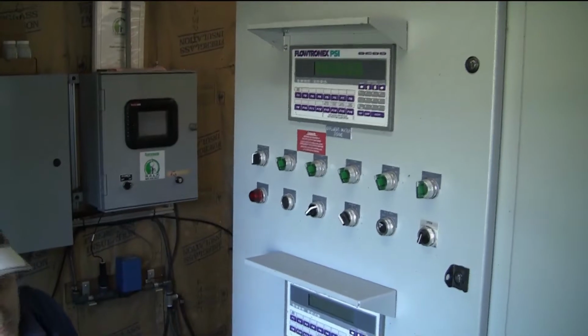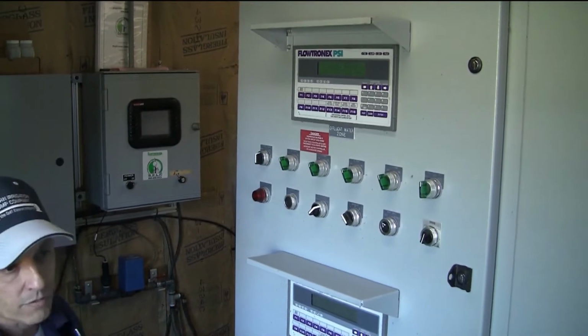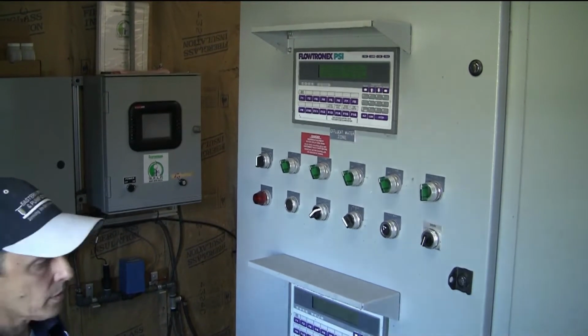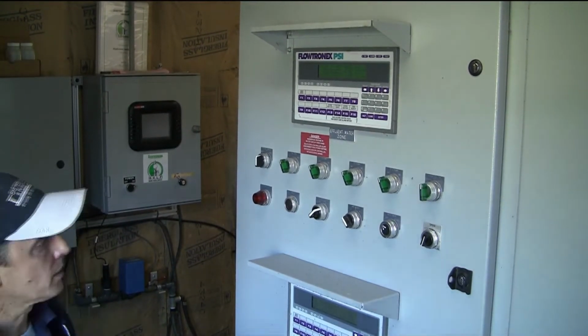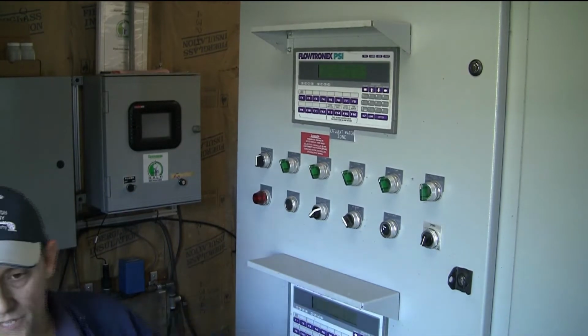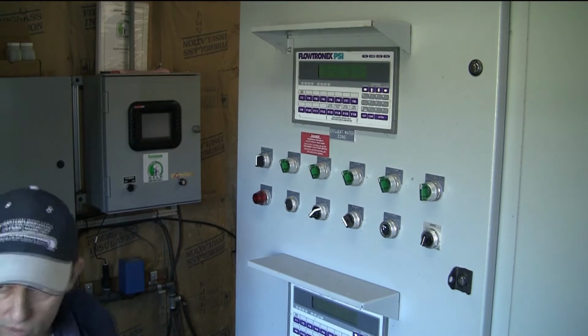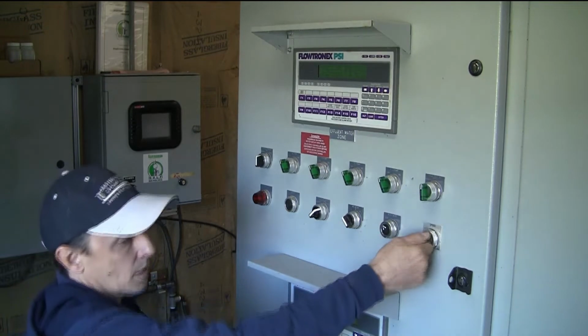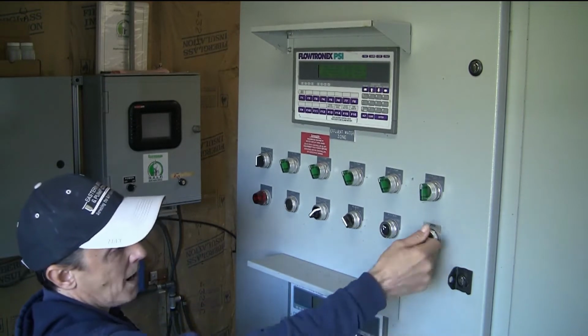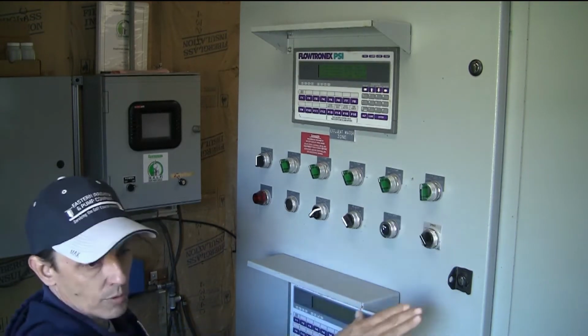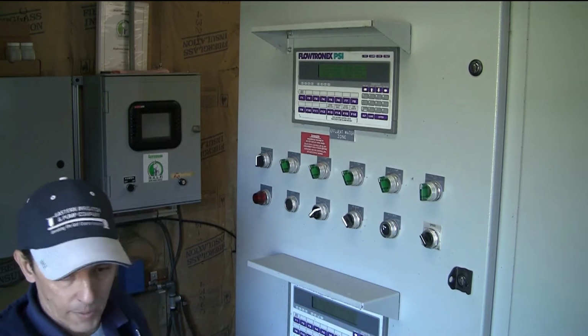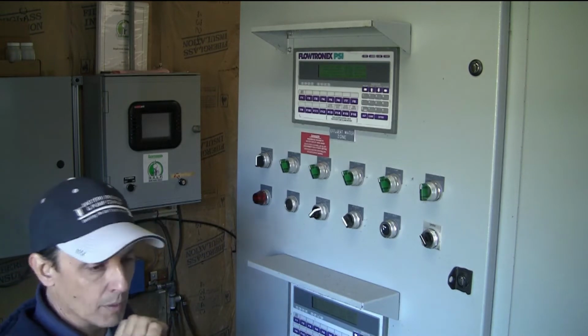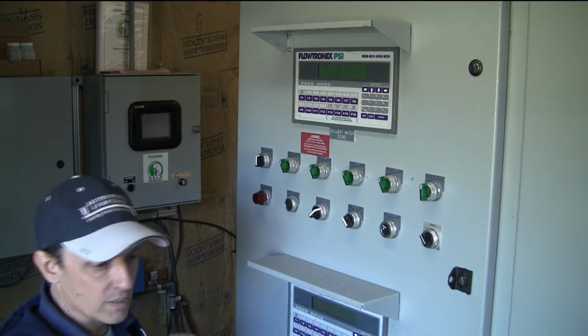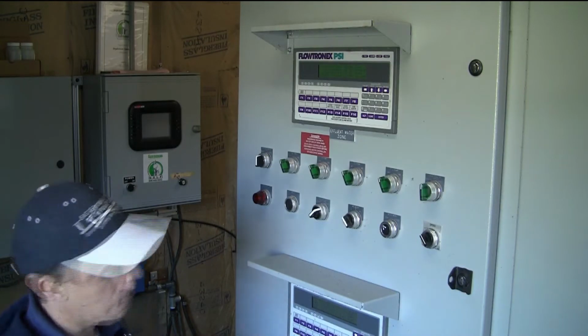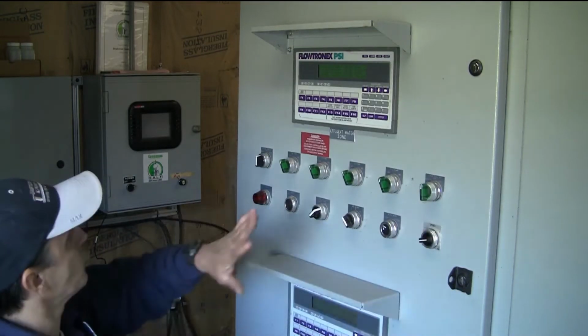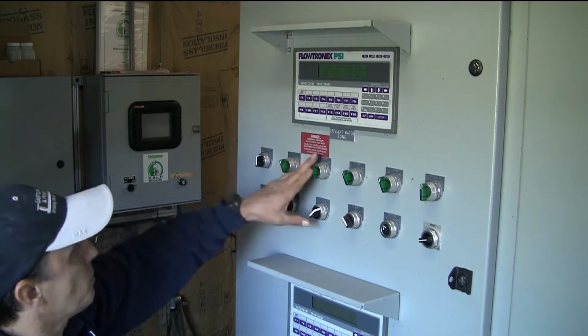Okay, now we're going to turn on each pump and run it through the VFD, manual through the VFD. We're not going to turn them on full speed. We're going to control it with what's called a speed pot. I'm going to increase the RPMs, and I'm going to see at what point the relief valve is going to open up. So we'll start with pump 1.